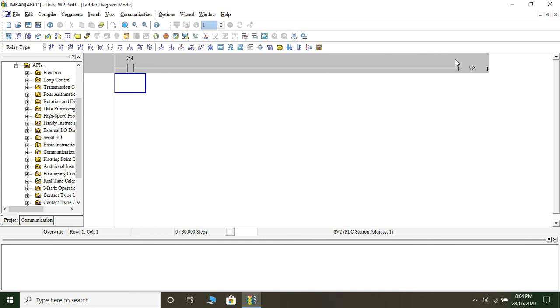If you see, the input is over here and the output has automatically gone to the extreme right. In your ladder diagram, the line to your left is called the left rail, and there's one more line to the right which is not visible, called the right rail. The horizontal line placed between the left rail and right rail is called a rung. Whatever input contacts or outputs you place will be on the rung between the left and right rail. You should make sure there is only one output contact in one rung.